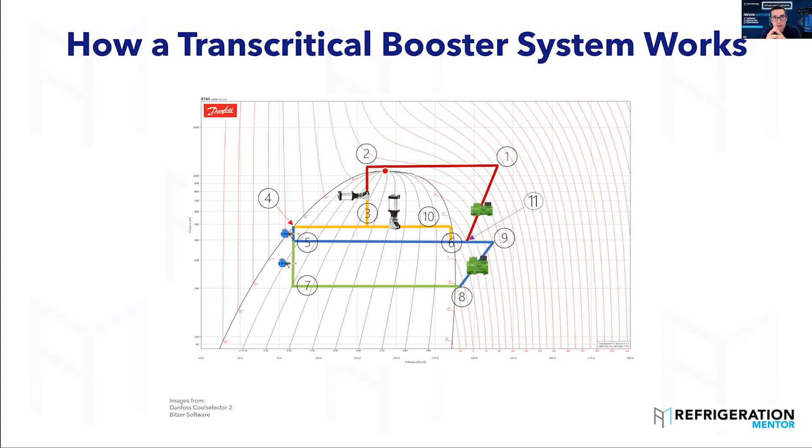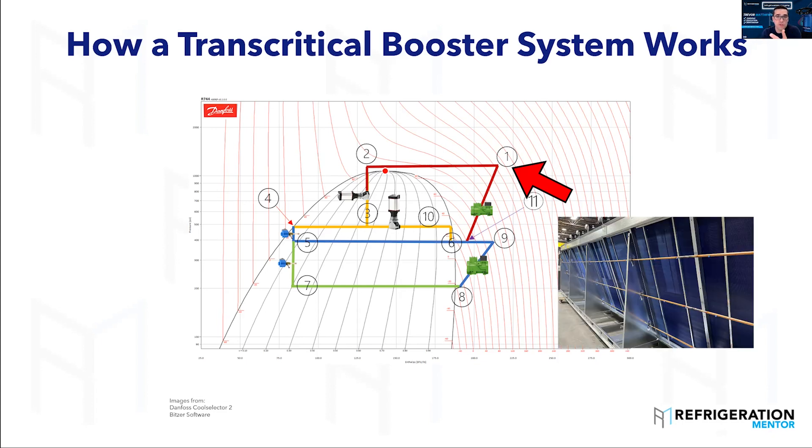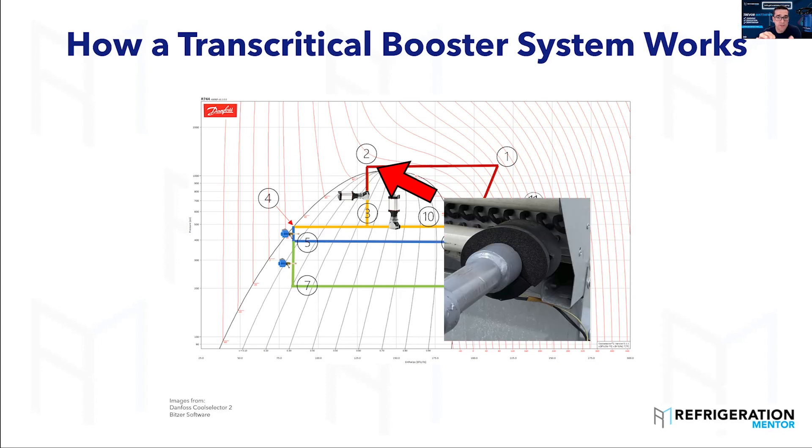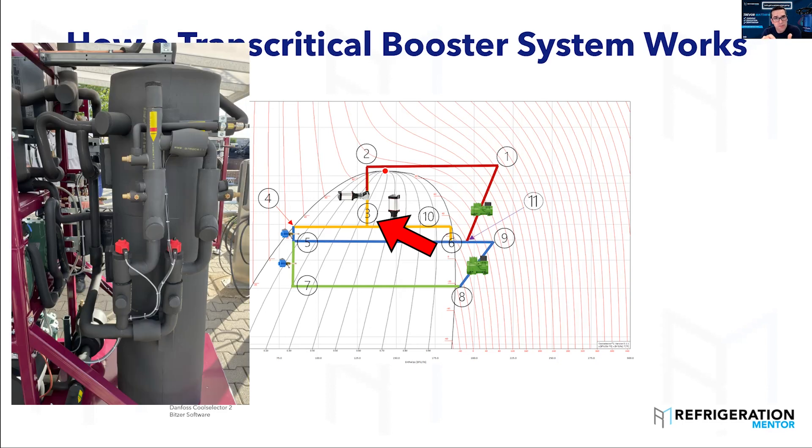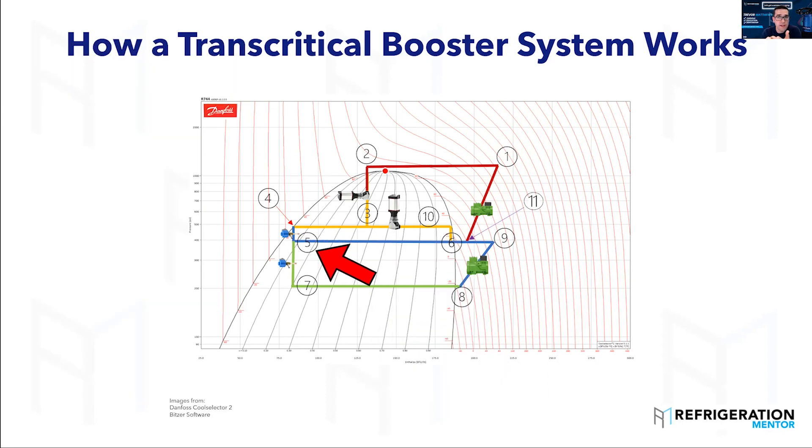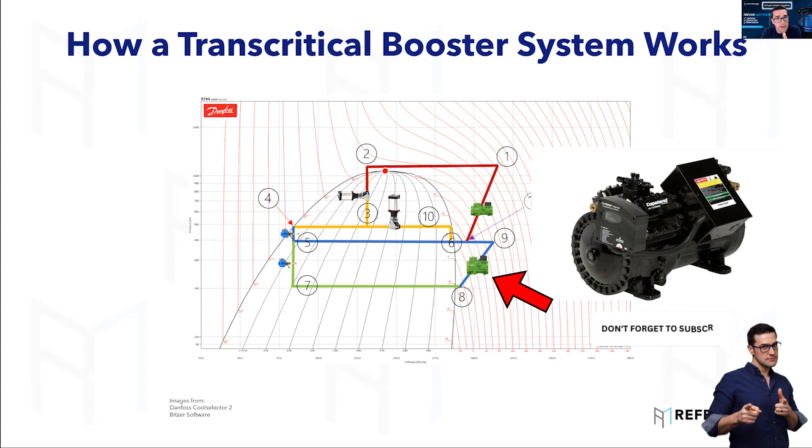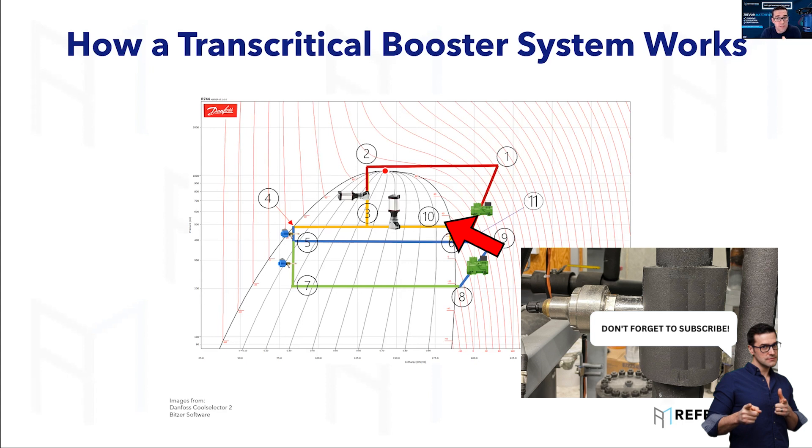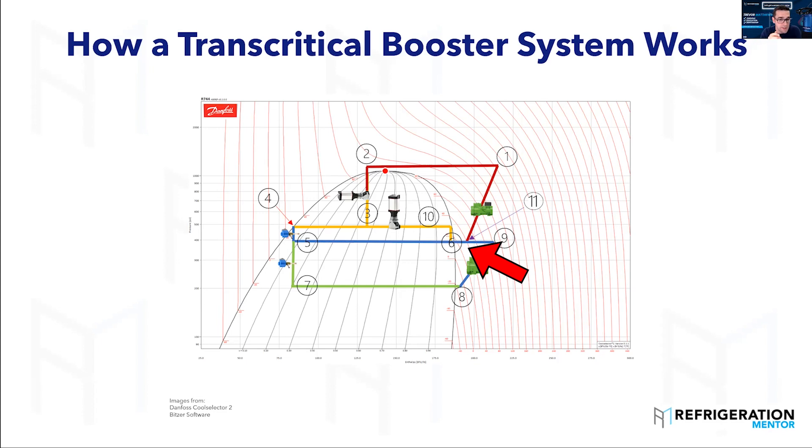And this is it. This is the step. This is how a transcritical booster system works. If you want to plot it again, for those who are listening, you have that medium-temp discharge. It goes up to your 1. Through your gas cooler condenser, outlet of that gas cooler condenser is 2. When you drop through the high-pressure valve, that is 3. Out of the liquid flash tank or receiver, you go to 4. That's the inlet of your metering device. 5 is the inlet of the evaporator. 6 is the outlet of the evaporator. 7 is the inlet of the low-temp evaporator. And 8 is the outlet of the low-temp evaporator. 9 is the discharge of the low-temp compressors. 10 is the flash gas bypass line. And 11 is all three lines together.